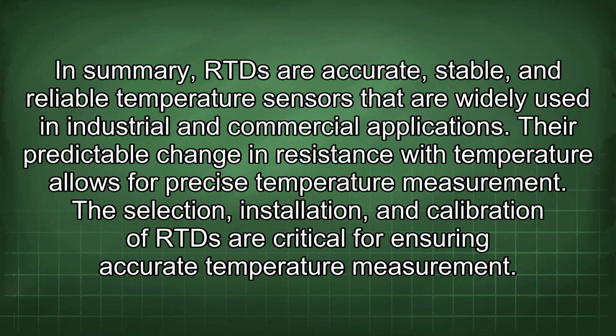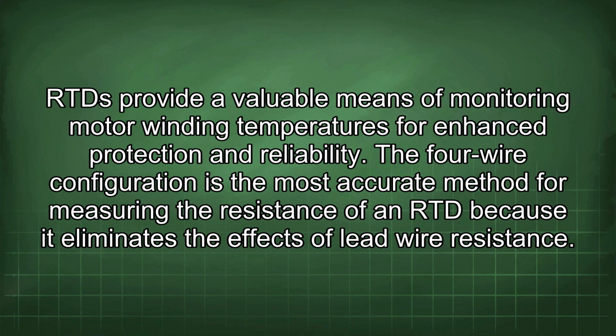In summary, RTD are accurate, stable, and reliable temperature sensors that are widely used in industrial and commercial applications. Their predictable change in resistance with temperature allows for precise temperature measurement. The selection, installation, and calibration of RTD are critical for ensuring accurate temperature measurement. RTD provide a valuable means of monitoring motor winding temperatures for enhanced protection and reliability.